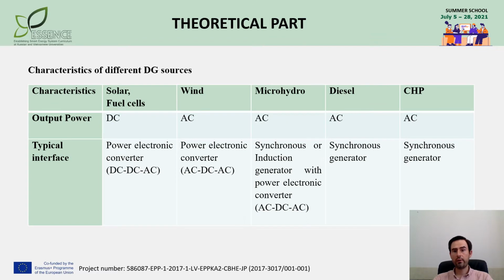When engineering a microgrid, it's necessary to keep in mind that different power sources may have different interfaces to connect with the AC grid, or alternating current grid. As just discussed, PV panels require stepping up the DC output and then converting the voltage into AC. The rest of the generators are electrical machines, but depending on the frequency of the primary mover, they also might be equipped with power electronic interfaces.